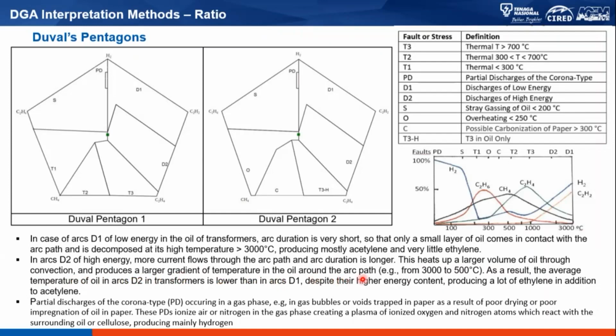Okay, and because the area is larger, the average temperature due to D2, as compared to D1, is lower because of the larger area that is involved. Despite the higher energy content of D2, it is still producing at a lower temperature because of the area that it covers, and because of that, it produces a lot of ethylene in addition to acetylene as well.